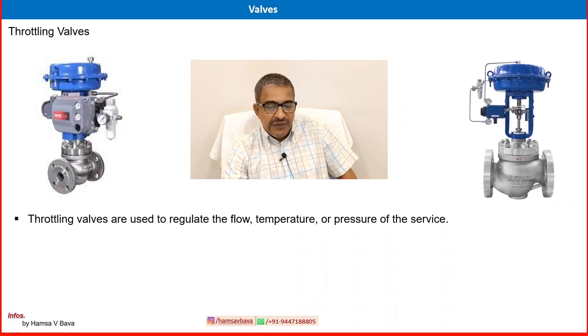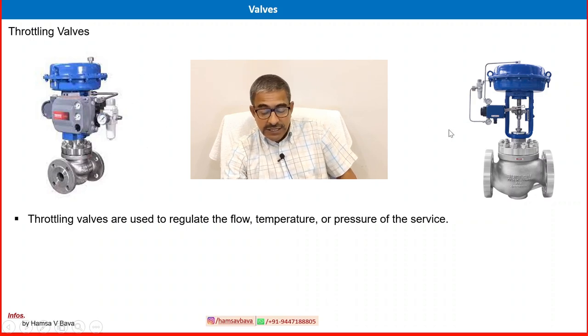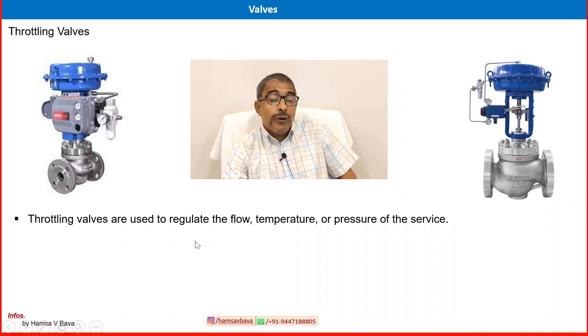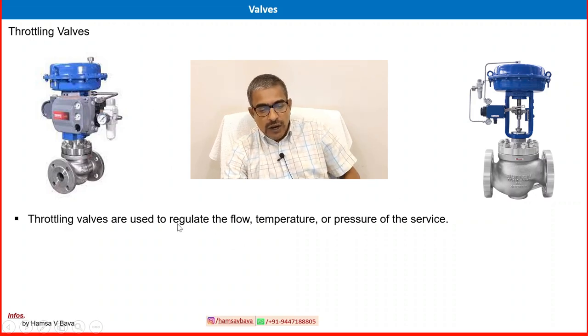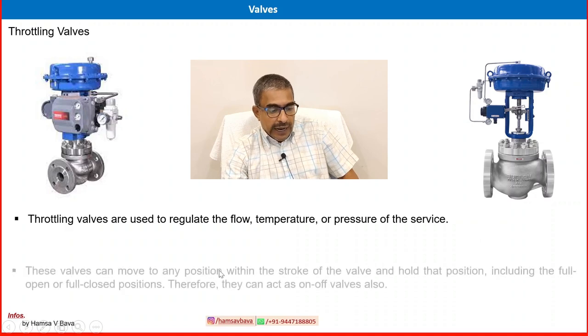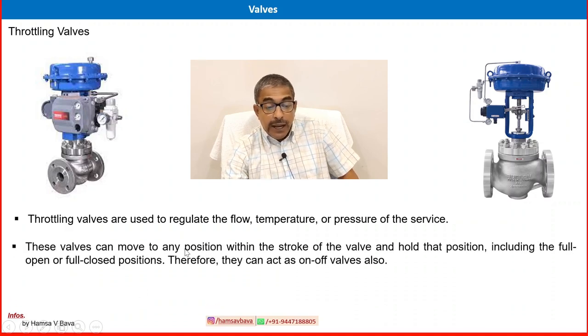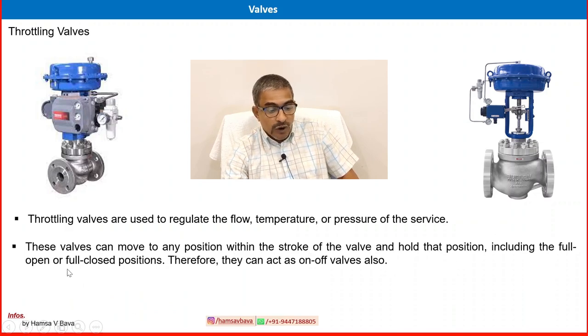The third category in functional classification is the throttling valve. There is a significant difference from non-return valves and on-off valves. Throttling valves are used to regulate the flow, temperature, or pressure of the process fluid. You can maintain, increase, and decrease the flow, pressure, or temperature. These valves can be moved to any position within the stroke of the valve and hold that position, including full open or full close. Therefore, they can act as an on-off valve.